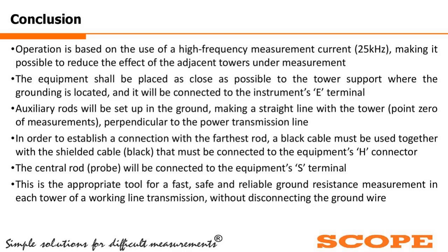In order to establish connection with the farthest rod, the black cable must be used together with the shielded cable, and the black cable must be connected to the equipment's H connector, or the current connector. The central rod or probe will be connected to the equipment's S terminal, or the voltage terminal. This is the appropriate tool for a safe and reliable ground resistance measurement at each tower of a working transmission line without disconnecting the ground wire.